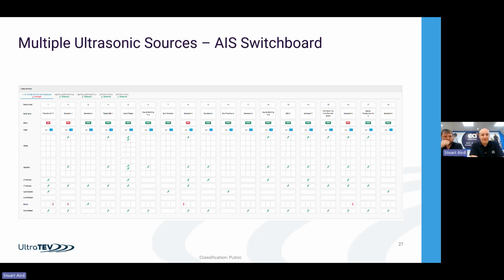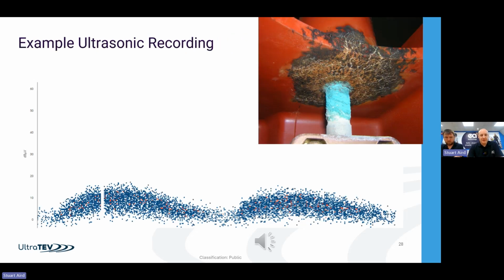It's generally down to the environment, so if you've got air insulated vertical racking type equipment, you want to try and keep the humidity in the substations as low as you can, particularly below about 40% if you can. And on this one we've got 4 different circuit breakers all discharging away. Again, I've got an example of the sound file that we recorded from one of those, you can hear it.